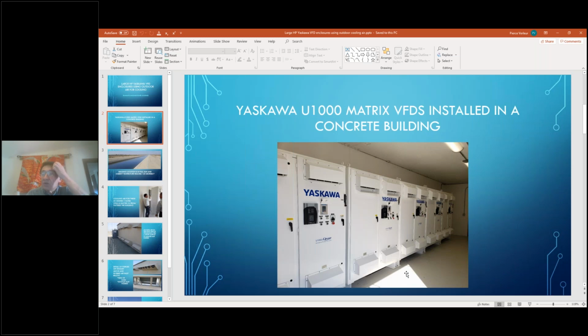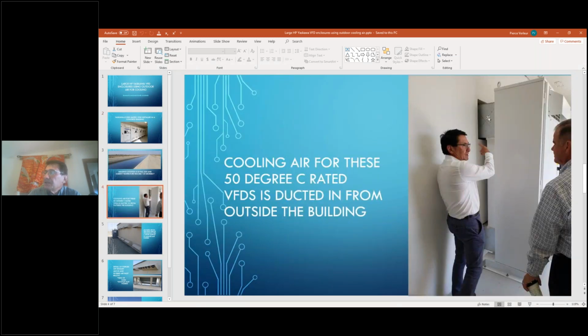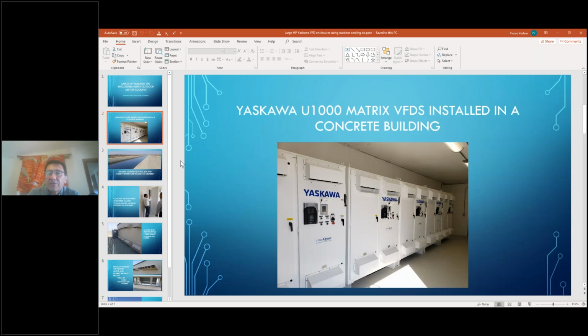The unique thing about this application is that the heatsink airflow, which is going up the back of the drive, so you can see the heatsink extended out here in this heat column, is not exhausting into the atmosphere of the building. These are standard NEMA 3R enclosures from Yaskawa. And the first question is, well, why are you using an outdoor duty enclosure in an indoor building that you spent all this money to build?